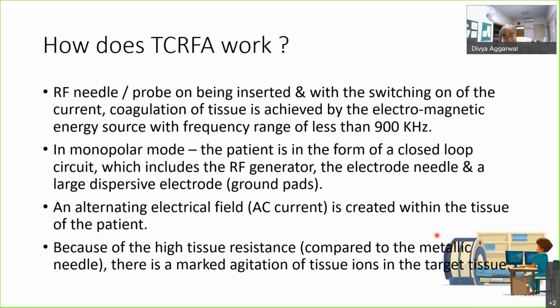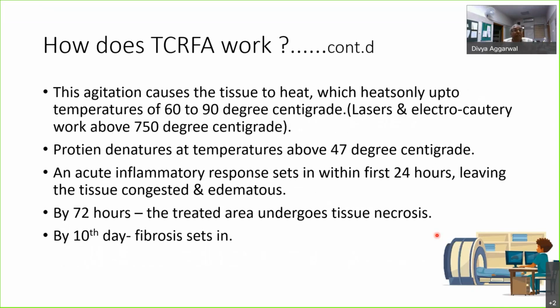Because of the high resistance compared to the metallic needle, there is a marked agitation of the tissue ions in the target tissue. Basically, what you have to remember as students is that due to the radio frequency, there is an agitation of the tissue ions in the target tissue that does the work for the radio frequency ablator. This ionic agitation causes the tissue to heat, only up to temperatures of 60 to 90 degrees. Mind you, lasers and electrocautery work at 750 degrees centigrade, whereas a radio frequency ablator works only at 60 to 90 degrees centigrade.